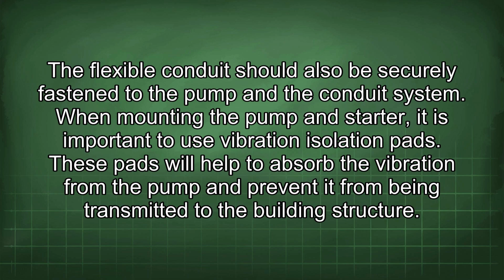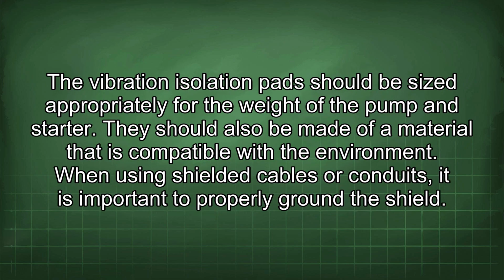When mounting the pump and starter, it is important to use vibration isolation pads. These pads will help to absorb the vibration from the pump and prevent it from being transmitted to the building structure. The vibration isolation pad should be sized appropriately for the weight of the pump and starter. They should also be made of a material that is compatible with the environment.